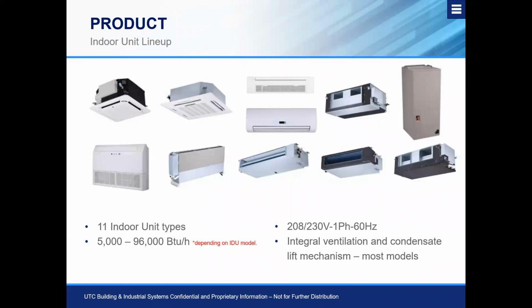They're all available in a 208, 230 single phase application, and we have integral ventilation and condensate lift mechanisms on most of the models. So for example, like we talked about before, the compact cassettes do have built-in condensate lifts. However, they have a maximum lift rating that we need to make sure that we do not exceed. Otherwise, we run the risk of overflowing the drain pan, and the unit will leak water.